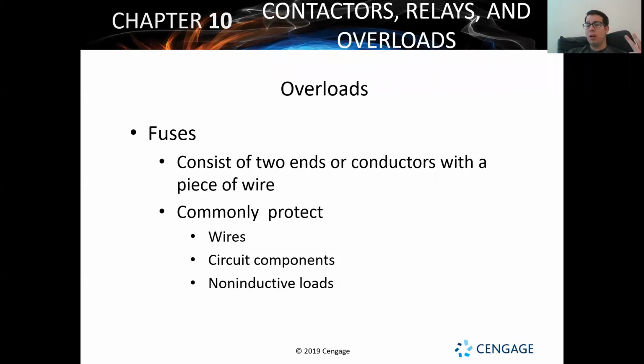People don't know how to install them. And so that is more of a safety for us as technicians. When it gets to the point where a fuse is going to pop in a system, it means that something majorly wrong is going on with that system, whether something is going wrong with the amount of amperage on the control side or on the load side. Our blower motor, our fan motor, condenser fan motor, our compressor, inducer draft motor, whatever it might be, all have it where they can have fuses in place for them. So again, fuse, most common type of overload.